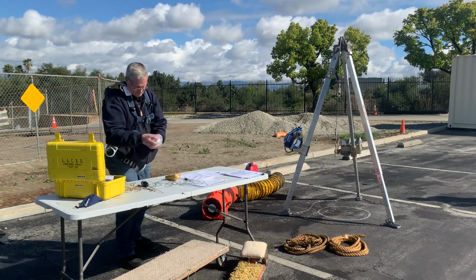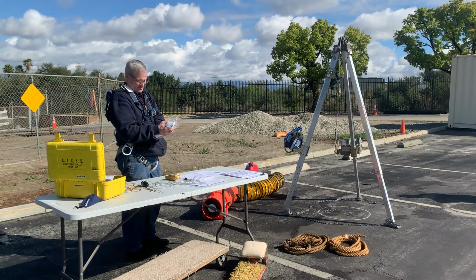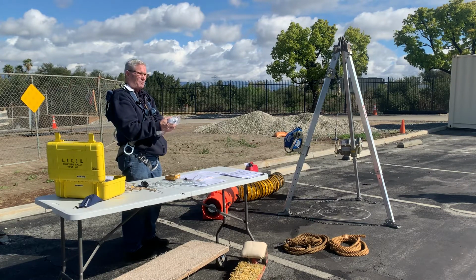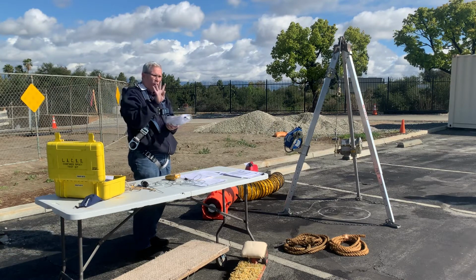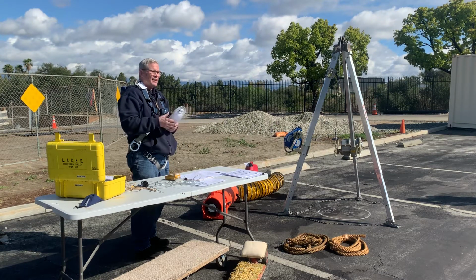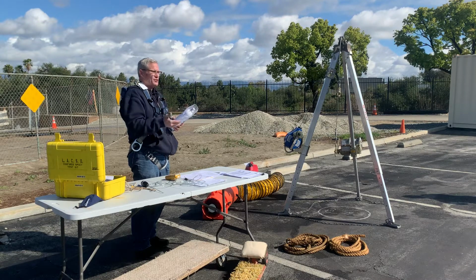And the bump gas, let me read that to you real quick. The H2S is at 75 parts per million, way above the 9. The carbon monoxide is 200 parts per million, again way above the 24. The explosive limit on this, methane, is 25%, way above the 9% allowed. And the oxygen is set at a lower level, 15%. All I wanted to say is that all 4 alarms should go off when I bump test this, and it's self-checking on that. If one of them doesn't, it will say error. It'll tell you which sensor.